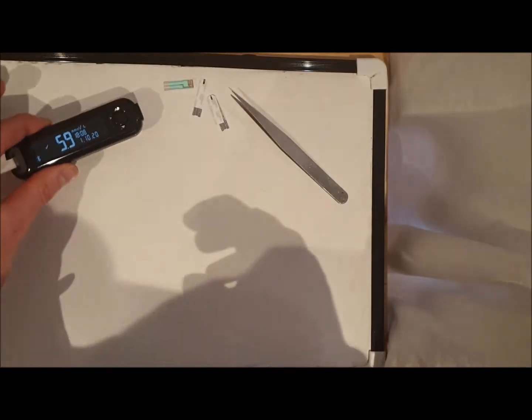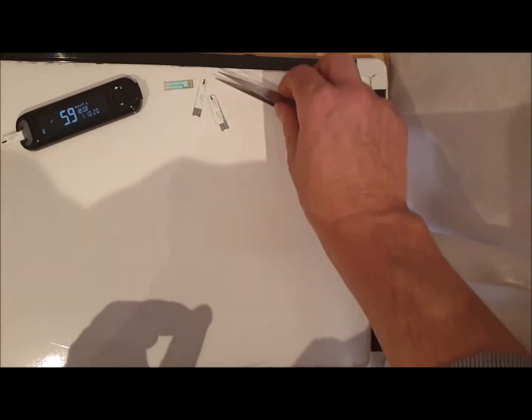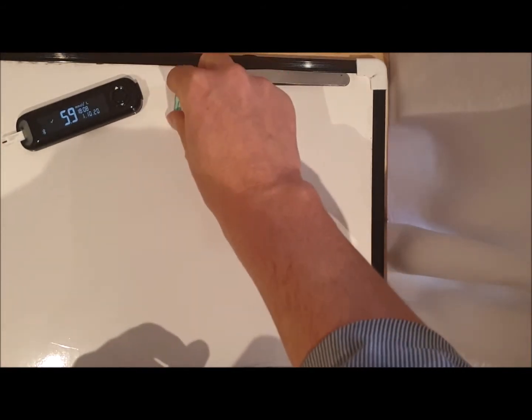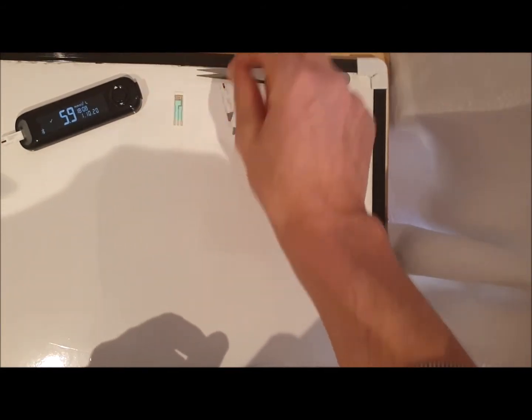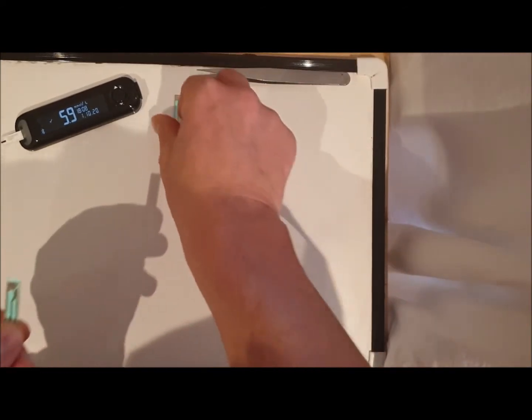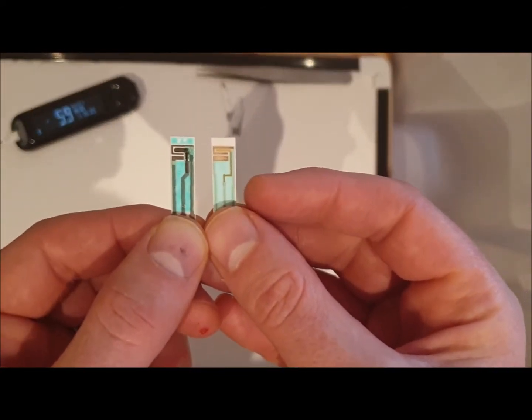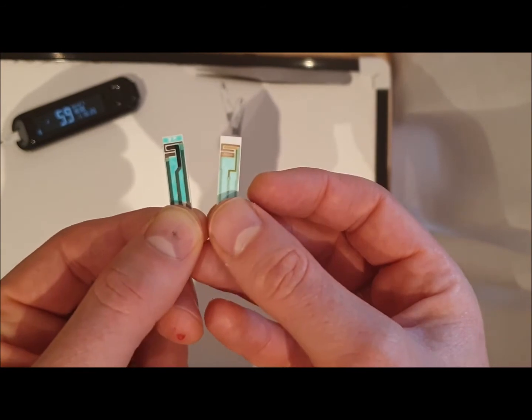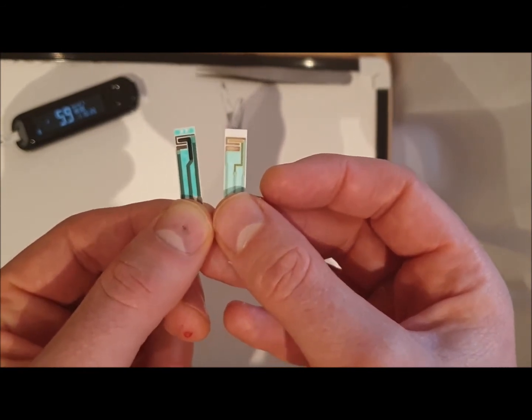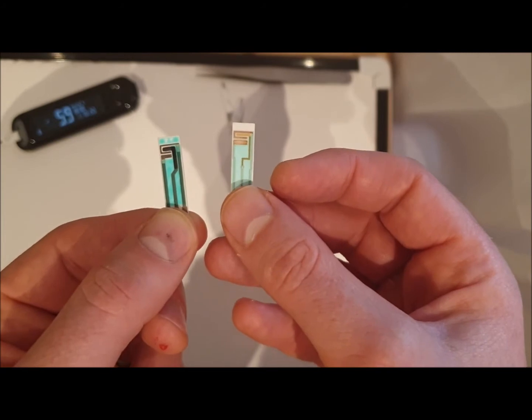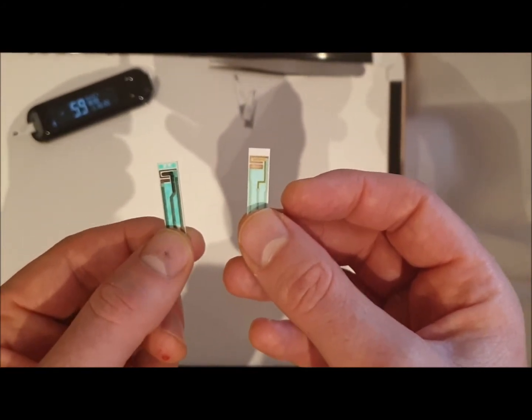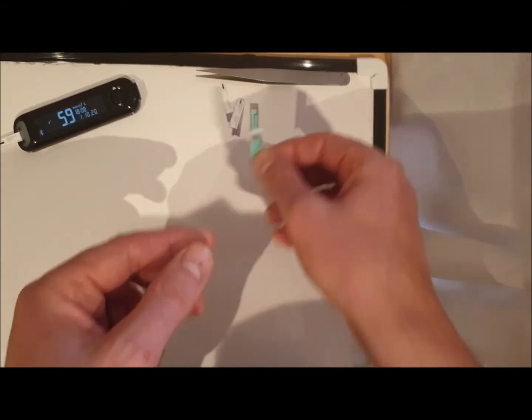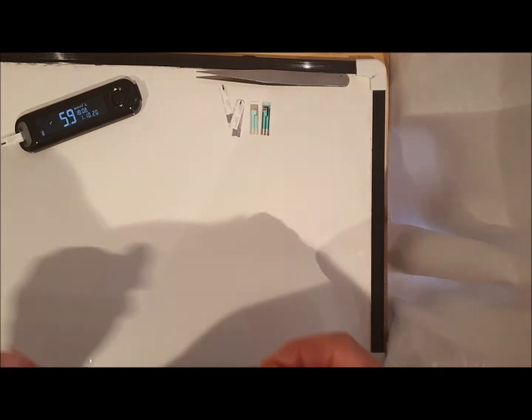We understand at Zimmer and Peacock that nobody needs another glucose strip for blood glucose monitoring. So what we have is we take many of the principles from the glucose strip world, but we manufacture screen printed electrodes—maybe a carbon one and maybe a gold one. If you're looking for these electrodes, I often refer to these as the carbon 303 and the gold 303. They're important because from these substrates people can develop and maybe even manufacture their own biosensor.